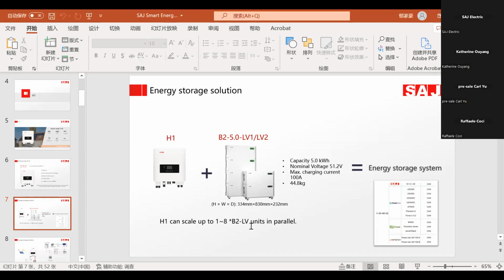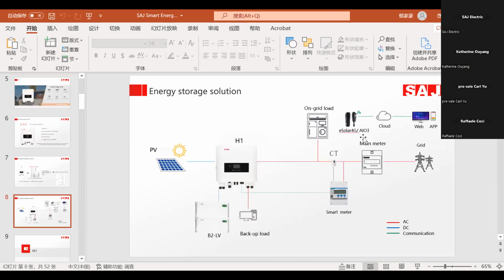The low voltage batteries are connected in parallel. It can connect 1 to 8 batteries, so the energy is from 5 kilowatt hour up to 40 kilowatt hour. Here is the working system of the hybrid inverters. The energy generated from the PV will feed the on-grid load and charge the batteries, and the surplus power will be exported to the grid. When there is no PV, the energy will be used from the batteries to feed the backup loads and also the on-grid loads. And we have 3 working modes for hybrid inverters, which I will introduce later.